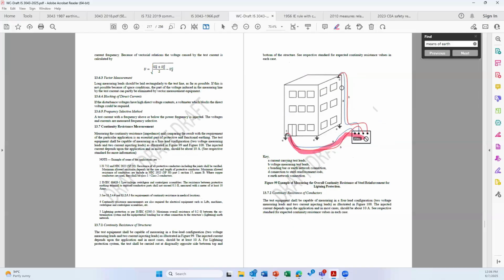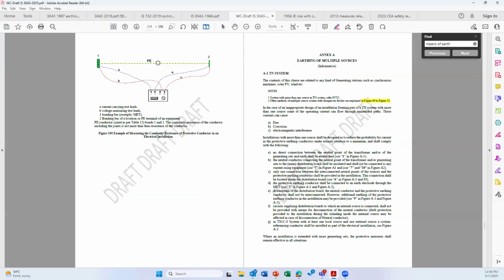Continuity resistance measurement, for example, in case of a lightning protection system, you need to measure the continuity resistance, and that is included. Continuity measurement in case of protective earthing in a building. Example, imagine you have a panel board. This is the panel board. And then you have a common bus bar in your industry. And now you are making a protective earthing, nothing but you take a wire and interconnect. Now the reliability of this connection is ensured by certain calculation and certain measurement that is included.